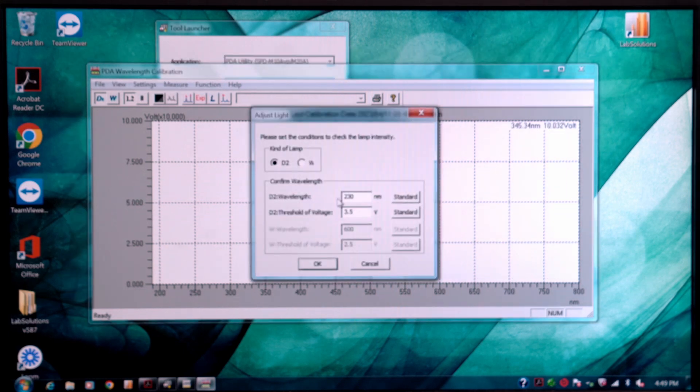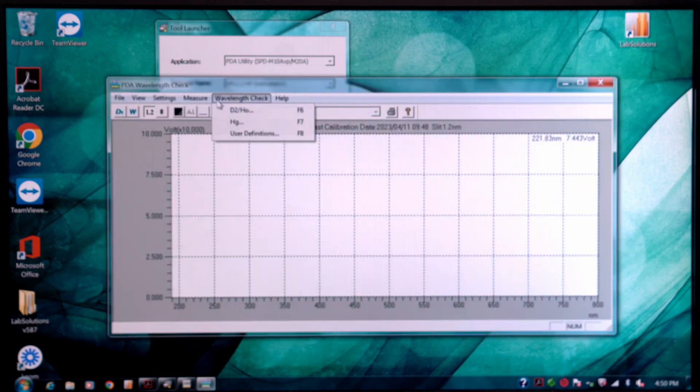The next thing you want to do is to check that the D2 wavelength is 230 and the threshold of voltage is 3.5 and the tungsten is 602.5. And if they're not, then change it to these values. And then after that's done, you want to go back and perform the wavelength check again. And then if everything passes, you're good to go.